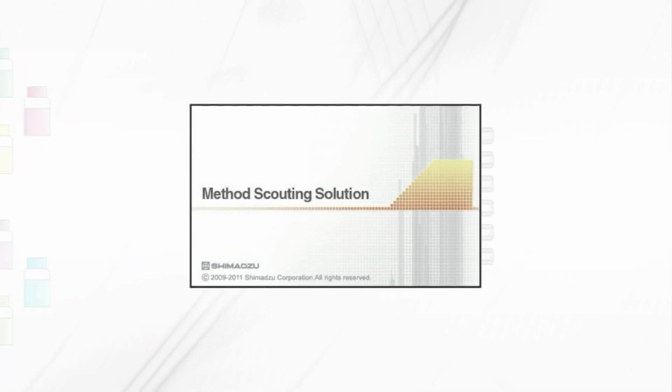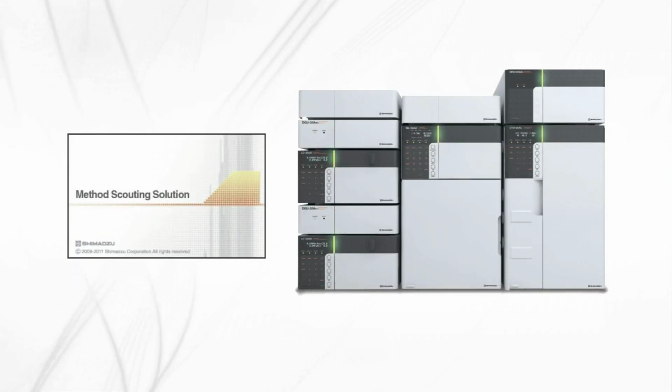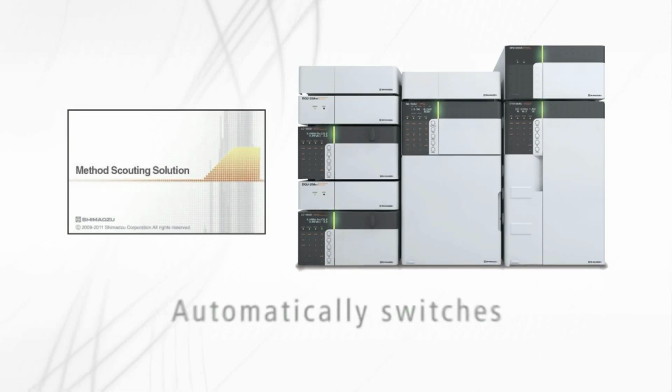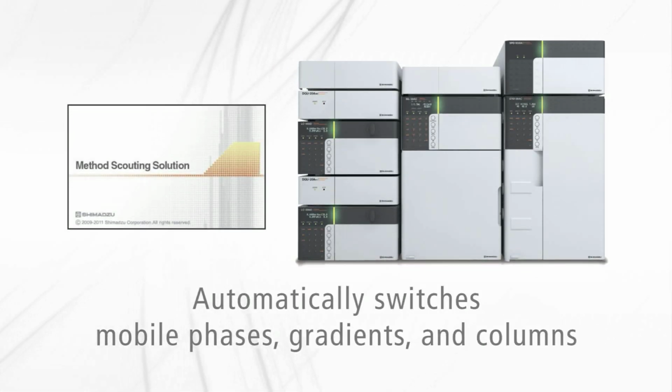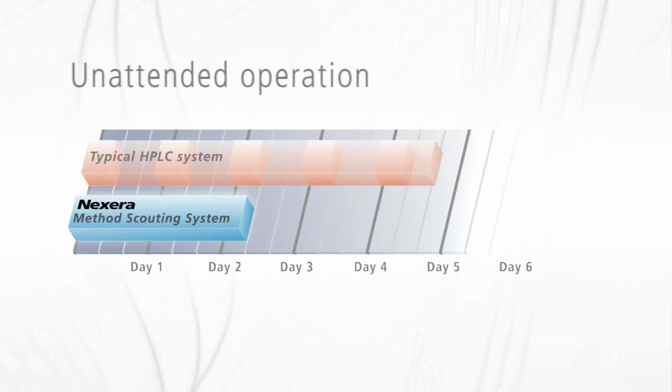It incorporates the specially developed Method Scouting Solution software, along with robust high-pressure compatible hardware, which is programmed to automatically switch mobile phases, gradients, and columns. The result is a quick and accurate, uninterrupted workflow, even during unattended operation at night.